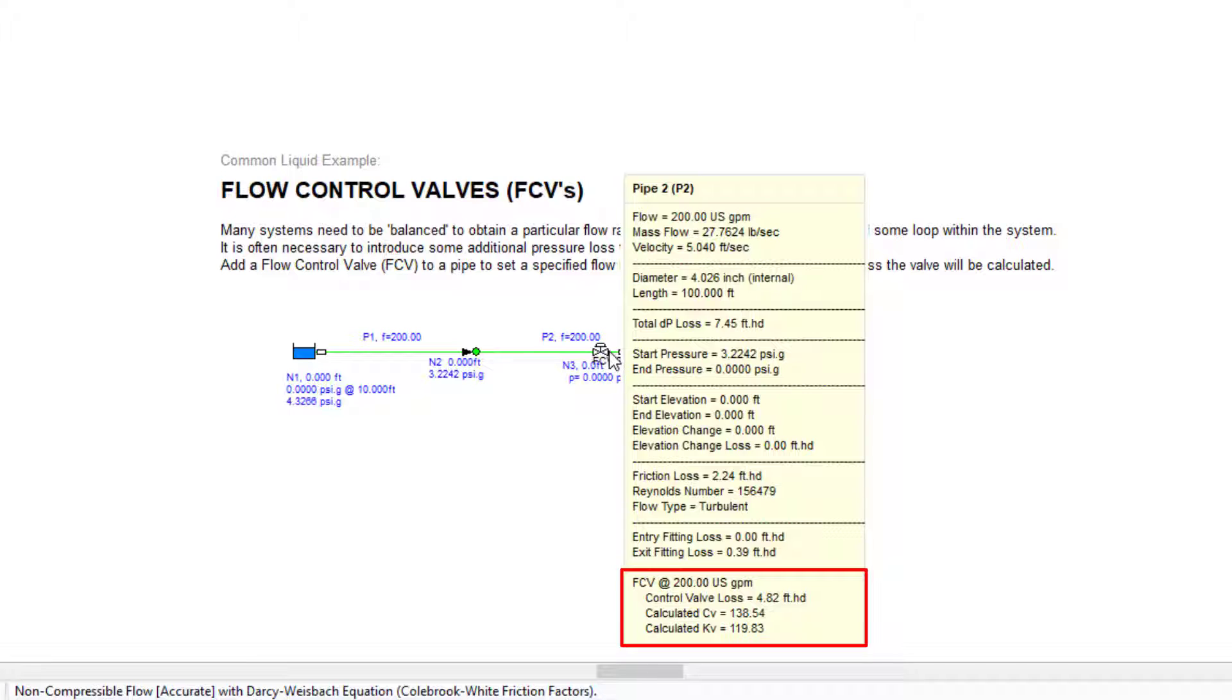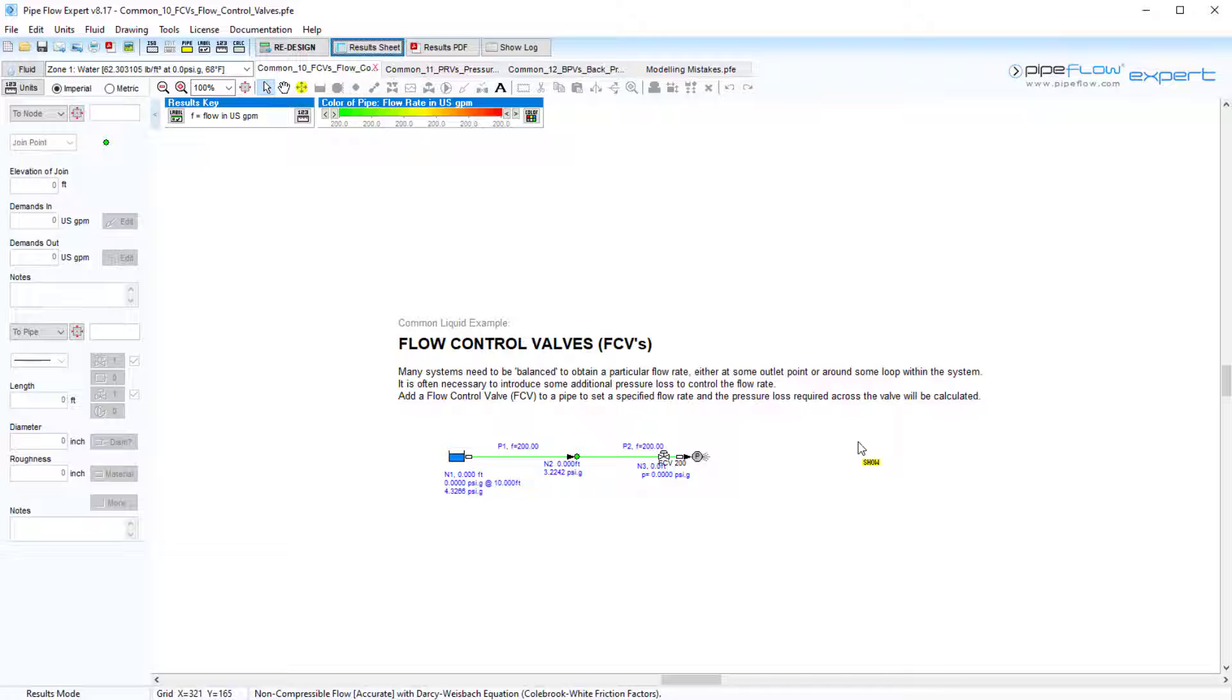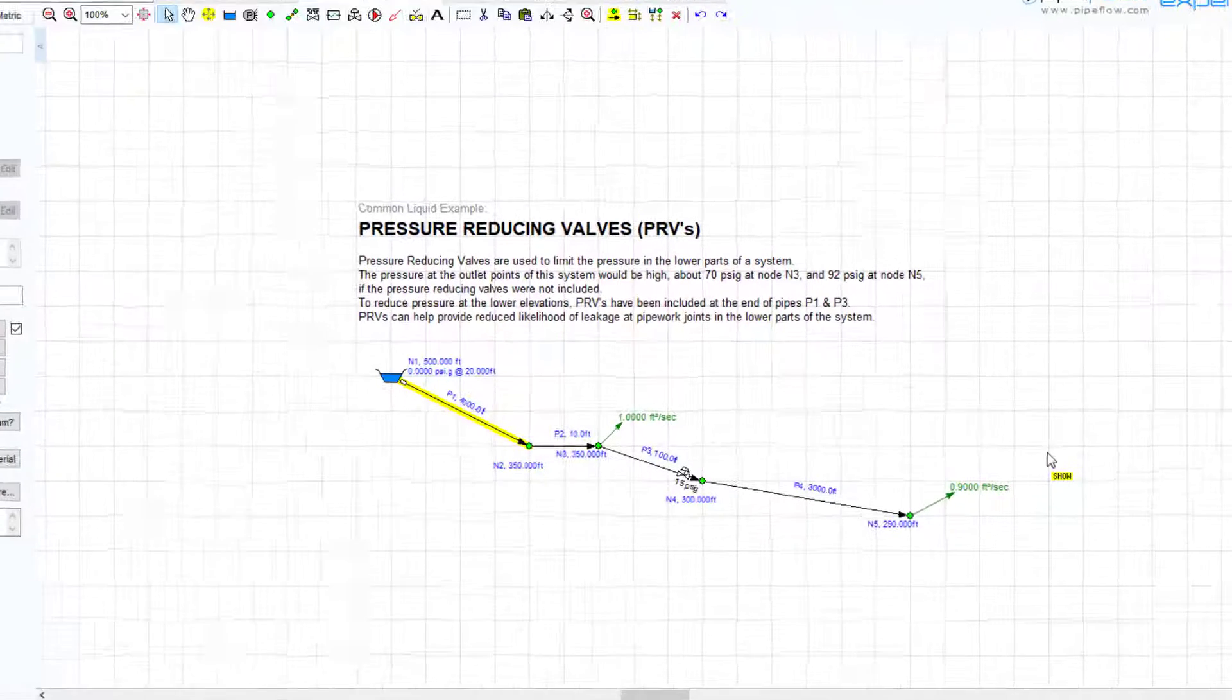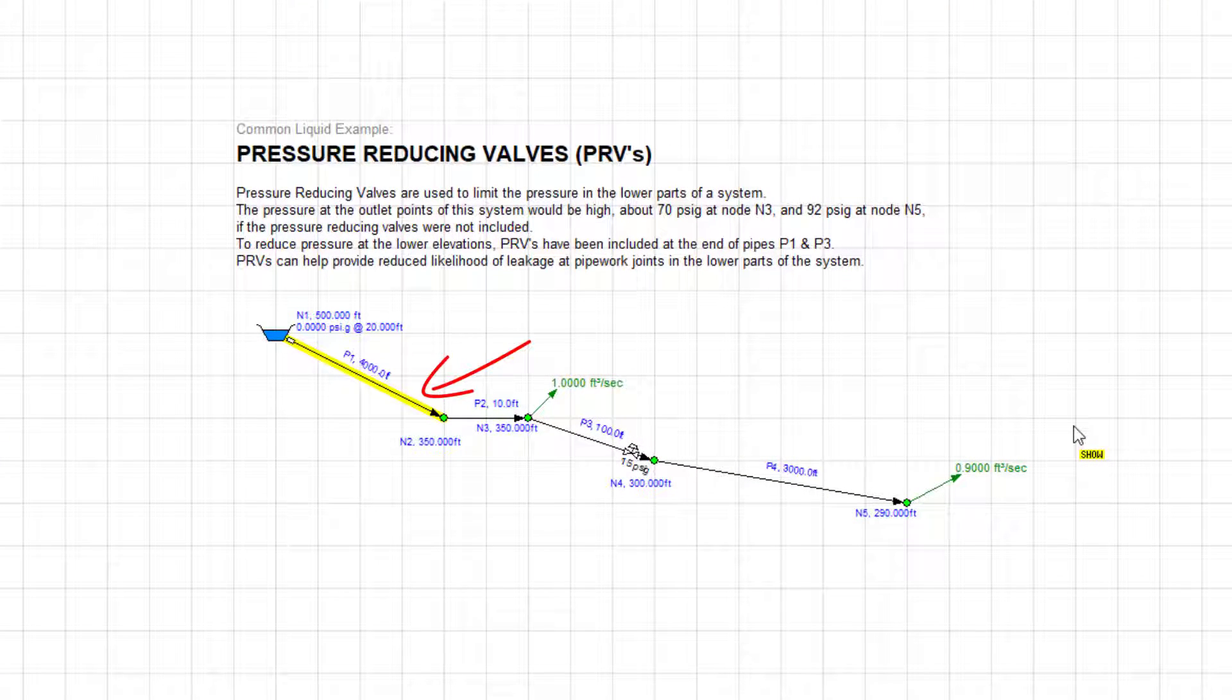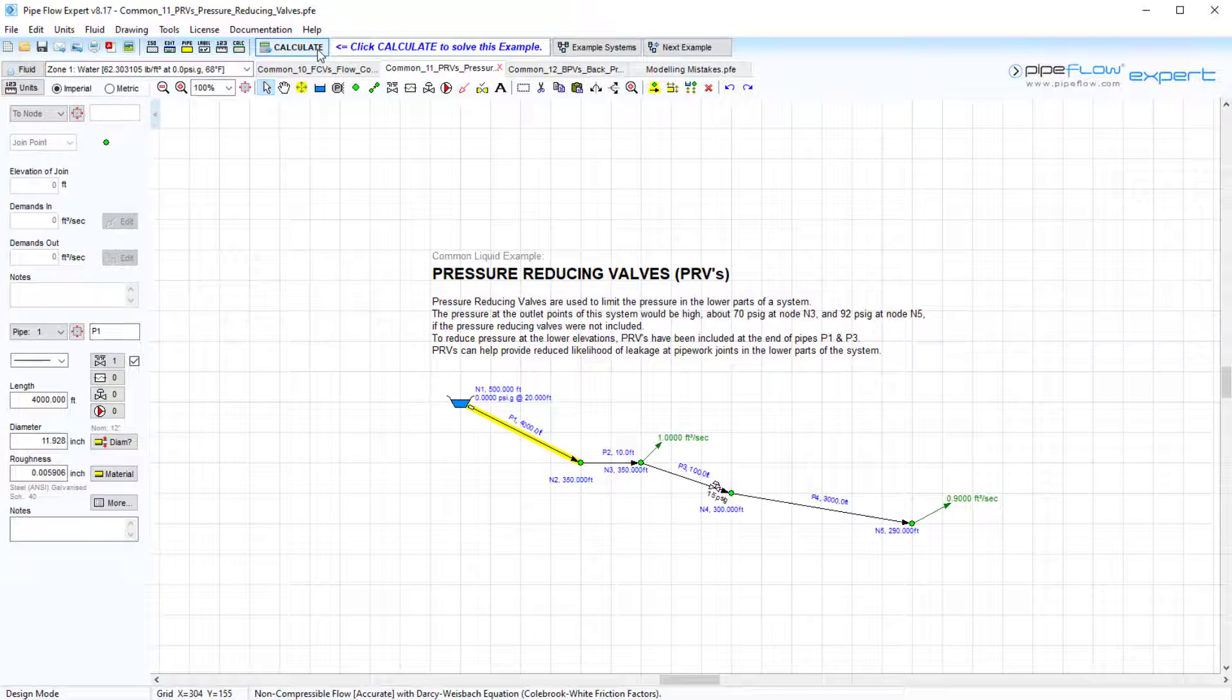Next, we will look at pressure reducing valves. Pressure reducing valves reduce the pressure at the end of the pipe by introducing a pressure loss. In this example, we will include a PRV on pipe 1 to reduce the pressure at the outlet node 2. Let's first calculate the model to see what maximal pressure we would get at this node.